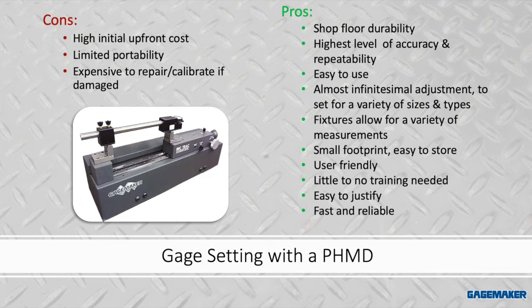Number one, the ease of use. There's nothing else like it. Dial in on a digital readout or an attached PC on a PHMD, the setting value with almost infinitesimal adjustment, too easy. The fixtures, I can't stress enough, using the fixtures to leverage the unit to its fullest capability just allows for such a variety of measurements and setting gauges, and later you'll see calibration. And you get to achieve all this without any loss in accuracy or repeatability. That's the key. It's fast and reliable, easy to use.